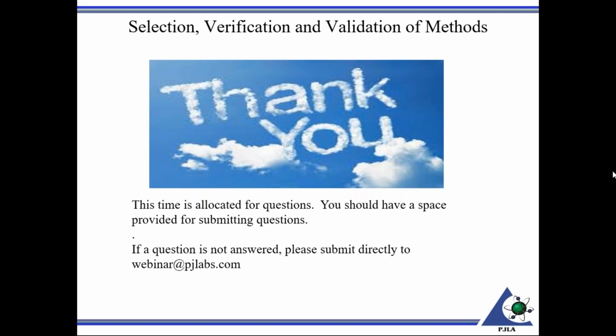This here is referring to breaking the calibration seal. In case of breaking the calibration seal to try to adjust the results, wouldn't the results already be rendered invalid as soon as you break the seal? I would say yes. Once you break that seal, then the integrity of that traceable calibration would come under question.